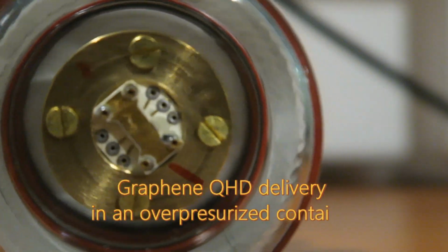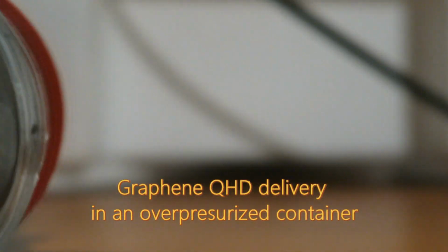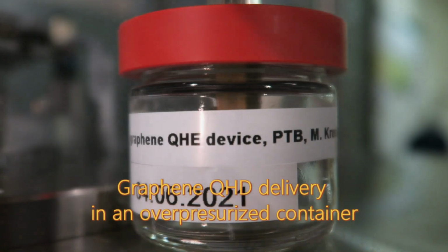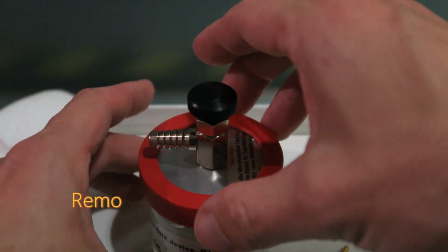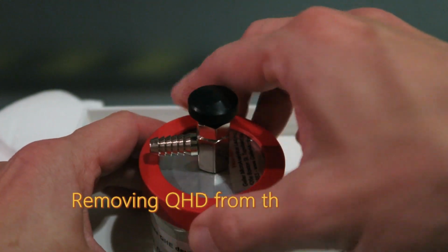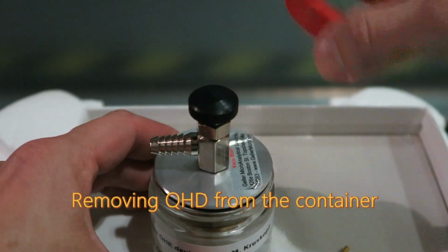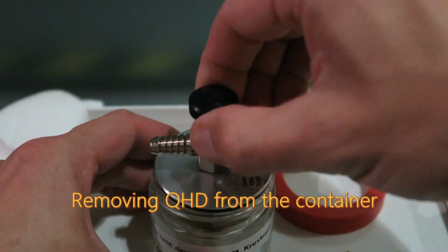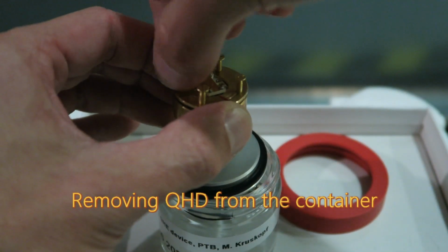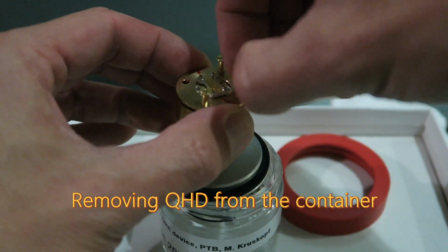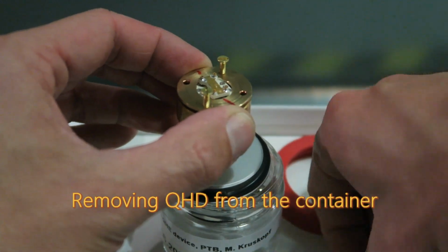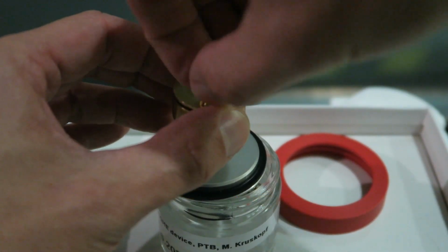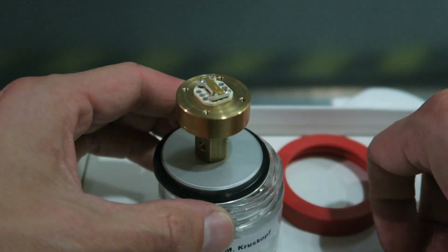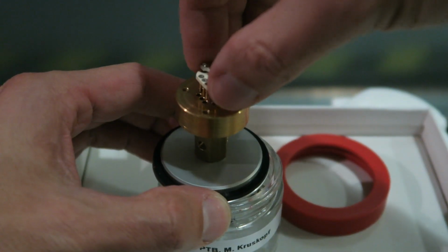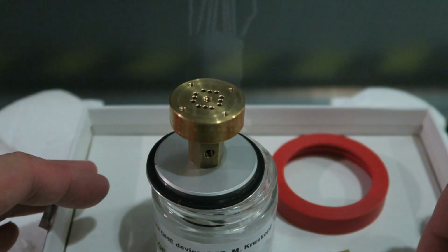The story begins with delivery of the device. We have received graphene sample in the overpressurized container. Such system is used by CRIS and PTB to protect devices against its contamination during the shipment. The container is filled with an inert gas. The device is mounted to conductive plate, so there is a protection against an electrostatic charge. Removing the device from the container is simple and straightforward.